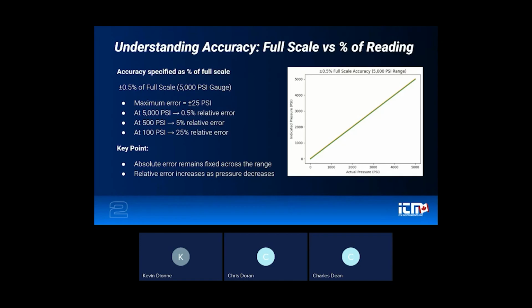So that may be completely acceptable for you, depending on your application. That being said, it's important to note that that same 25 PSI error still applies at lower pressures. So if that measurement instrument is being used to measure 500 PSI, then the absolute error still remains 25 PSI. This is where accuracy specifications must be evaluated in context. The question isn't whether the instrument meets its stated accuracy, but whether that accuracy is appropriate for the pressure range and the tolerance requirements of your specific application.